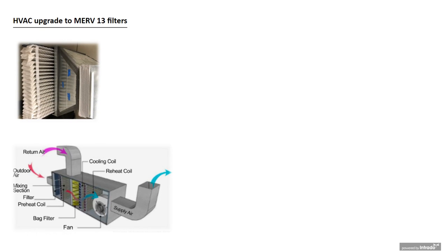The next technology is an upgrade to the building's ventilation system or upgrade to MERV 13 filters. Now again, we understand how ventilation works, and if you don't, there's a quick diagram here. You have outside air that comes in, that gets processed, it gets filtered, and then you have supply air, which is air that enters the room. Then you have return air, which is the dirty air, the processed air that is returned back into the HVAC system, and it's a continuous process.